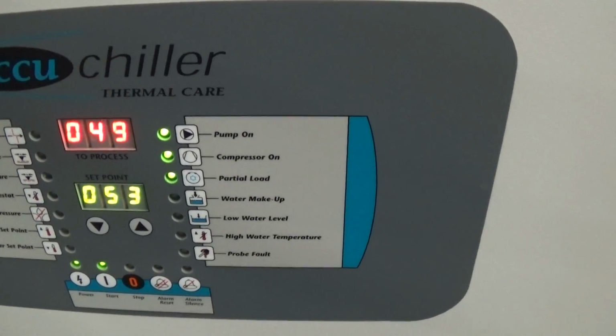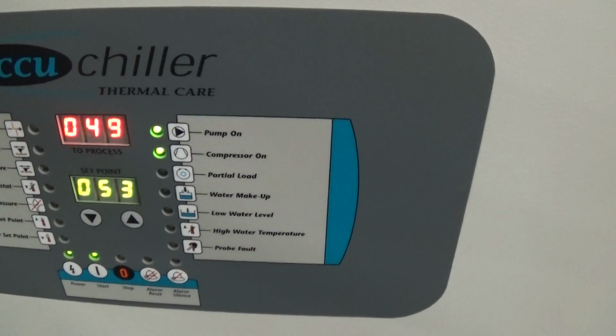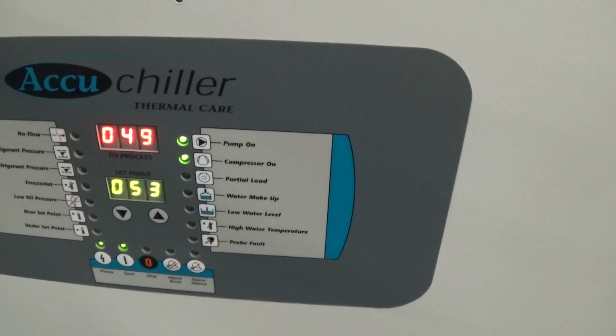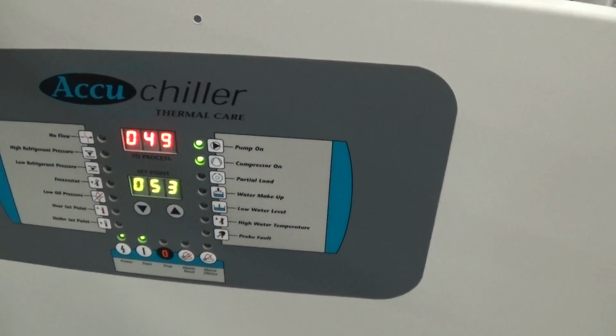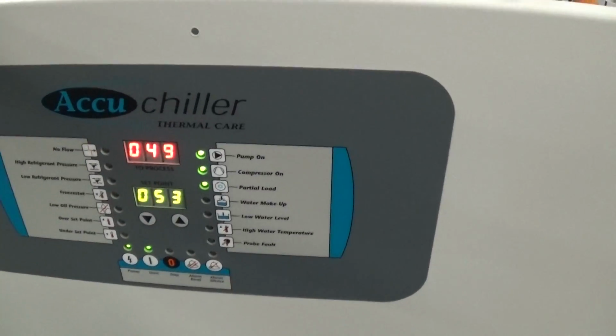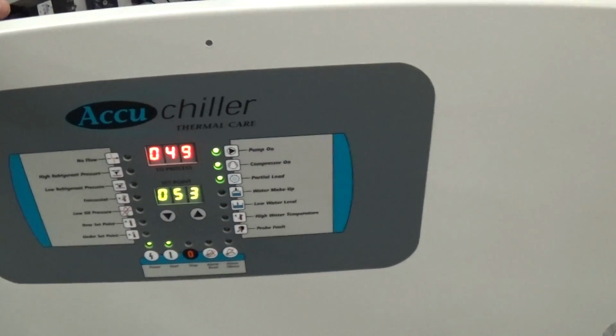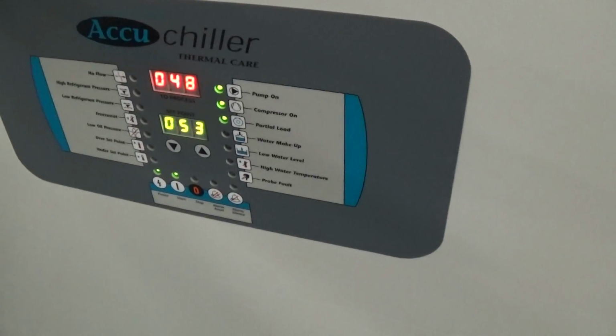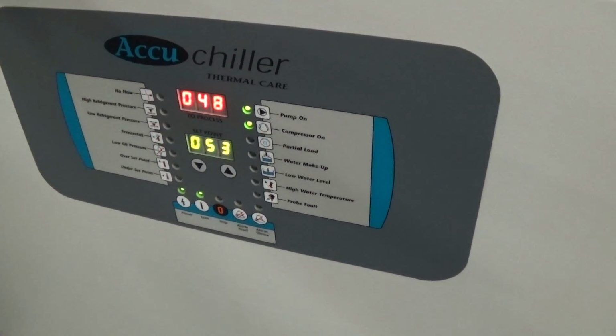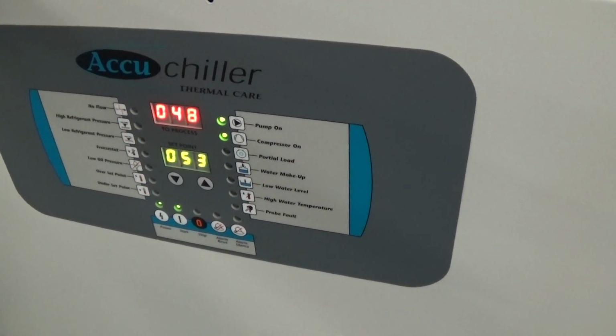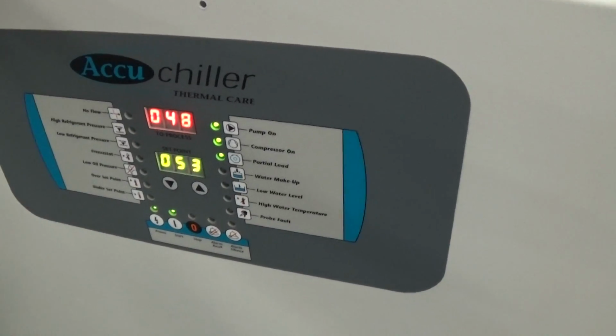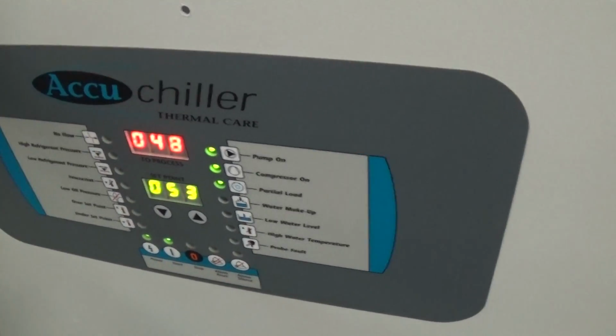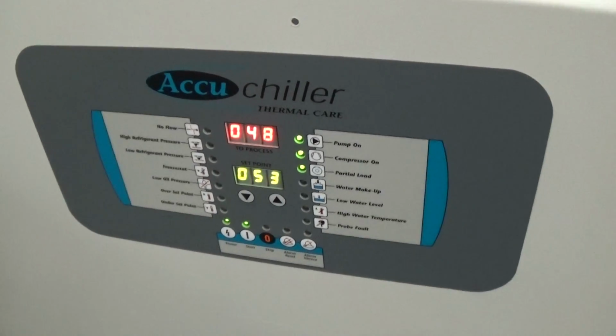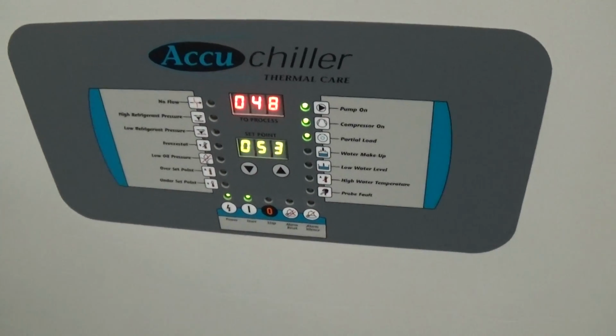So now you can see our hot gas bypass is coming on. And what that does is that kind of creates an artificial load, bypassing some of the refrigerant to keep the compressor running a little bit longer. That logic is to reduce the amount of starts and stops on a compressor. A compressor likes to be running. It's the starts and stops that wear out or put a heavy load on a compressor.